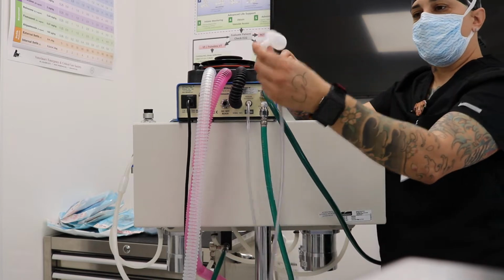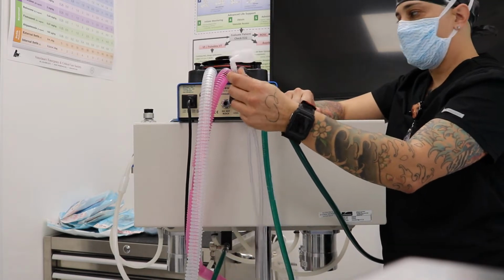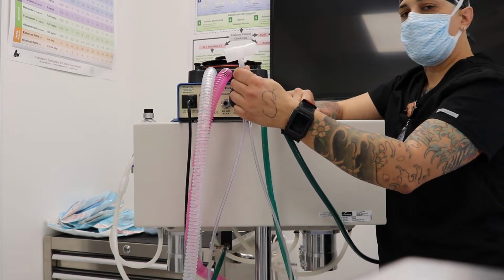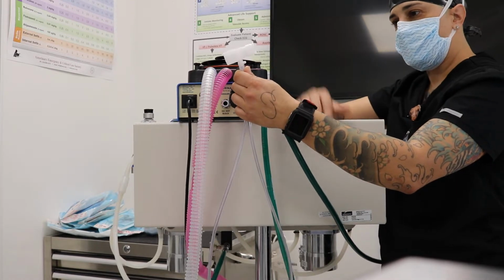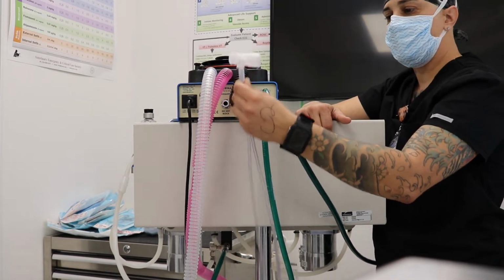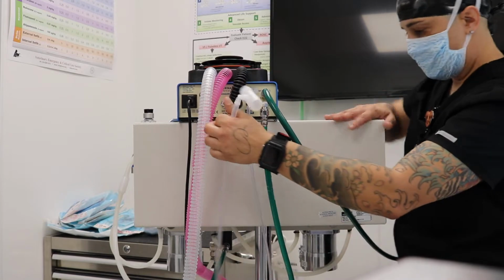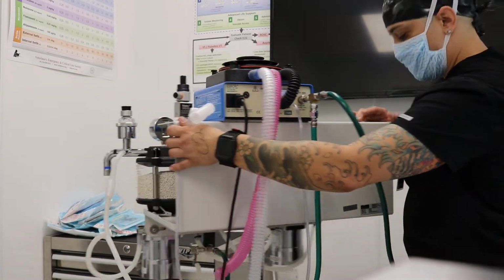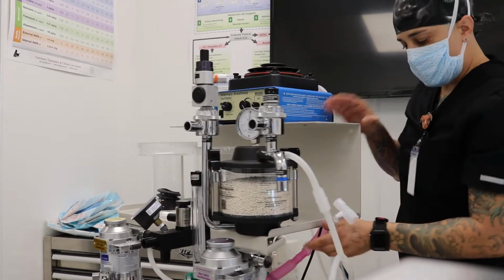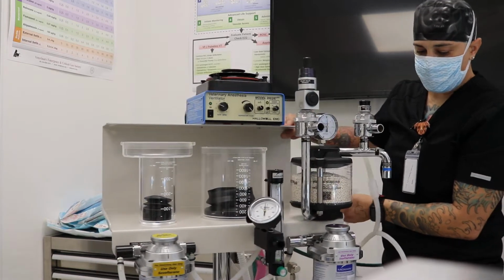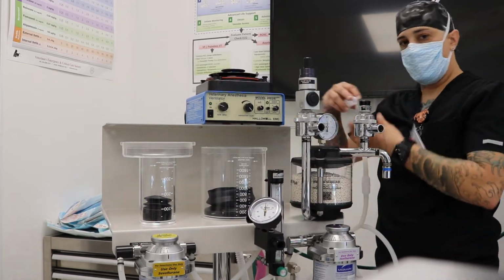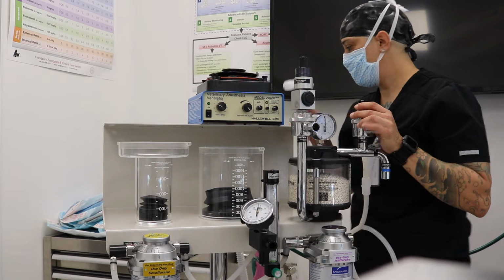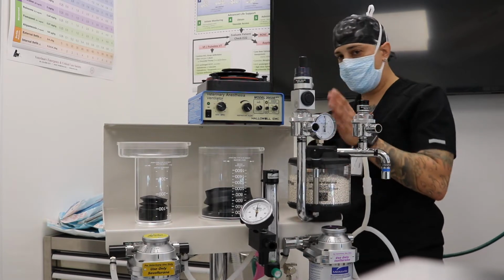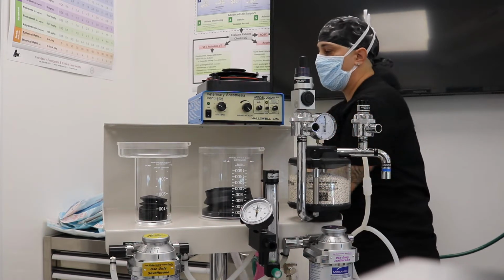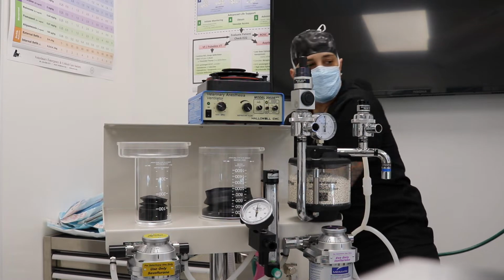This right here is our transducer. So this is our pressure transducer. Without our pressure transducer, the bellow won't work, the bellow won't depress because it does not know how much pressure it's being told. So let me turn this around. We're going to do a leak check, and I'm going to show you the sound you're going to hear when you don't have the pressure transducer connected, so that you know when you hear that sound, what that sound means and what you need to do to fix it promptly.